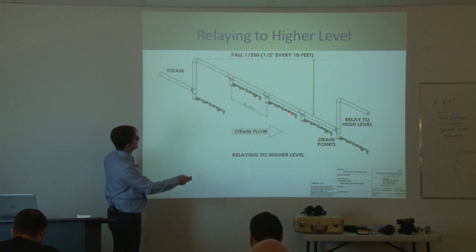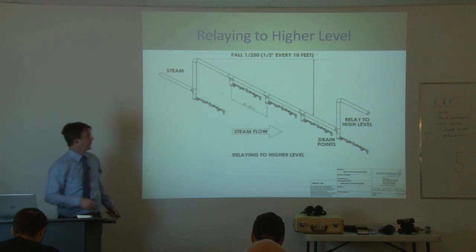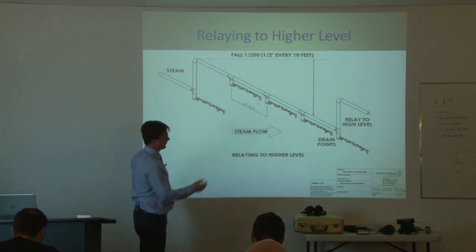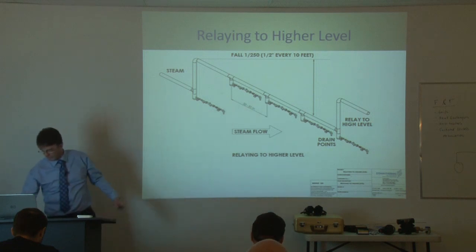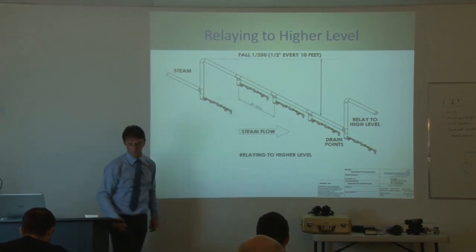So we want to have a trap wherever we have a change in direction, and also we want to have steam traps along the main. So we want to have an adequate number of steam traps. And these are things that I look for when I'm doing trap audits as well. So if you're out in the field and customers complaining of different problems, these are things to look for.